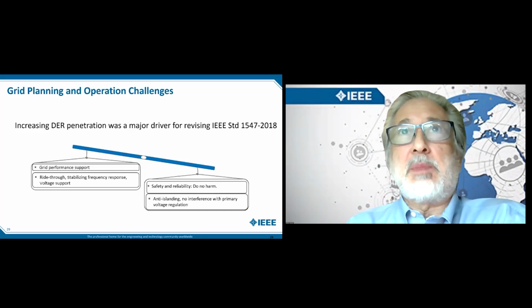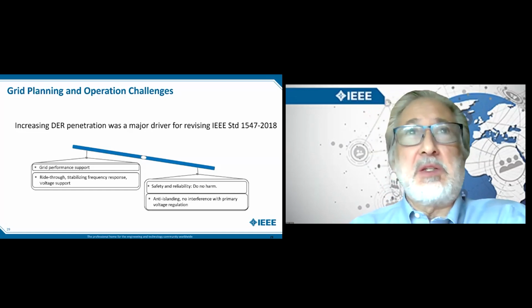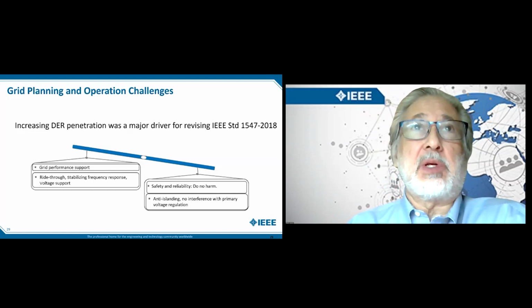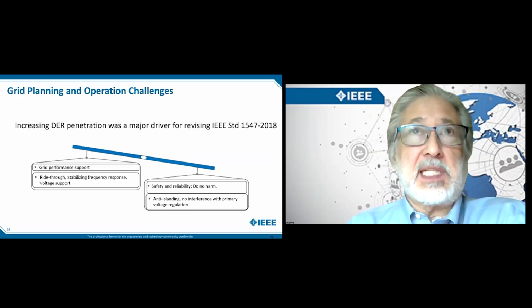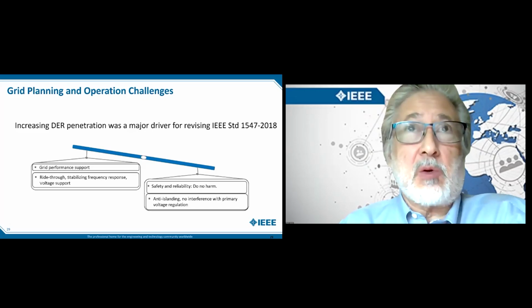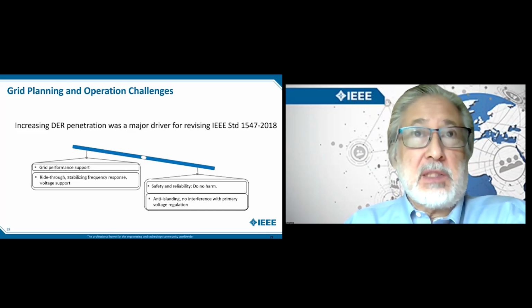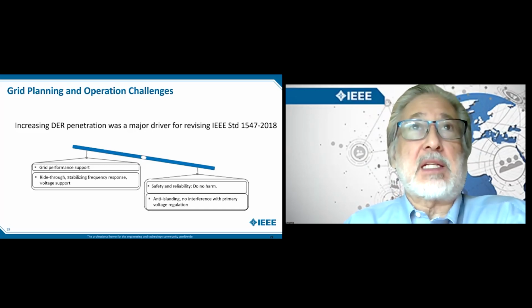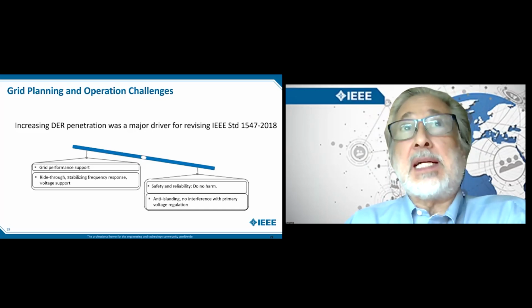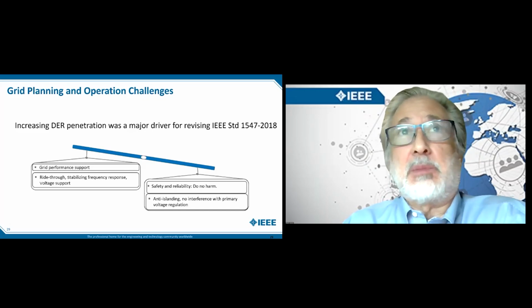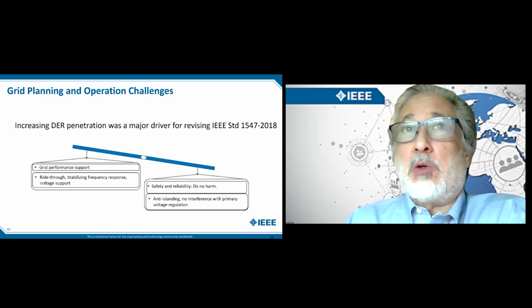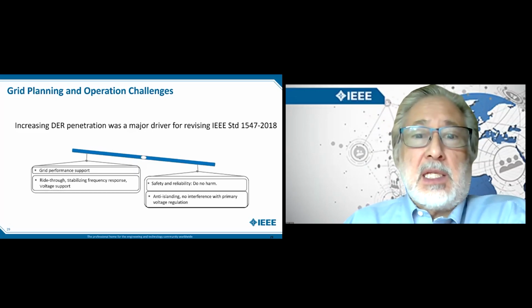If you followed the requirements, there was some confidence that you would not degrade the reliability of the grid. For example, the voltage control requirement of 1547-2003 was unity power factor — meaning the DER was not to interact with the grid for purposes of maintaining local or area voltage.